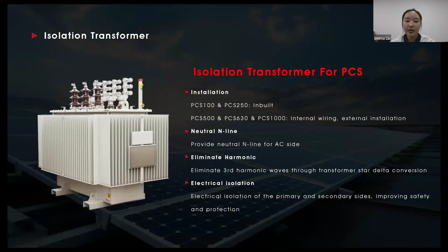One of the unique features of ATESS inverters is the isolation transformer. A PCS inverter used for a large-scale system must be equipped with an isolation transformer. It can provide neutral and line for the AC side, eliminate harmonic waves, and improve safety and protection. The isolation transformer of PCS 100 kilowatt and 250 is built in, and the other 3 models, 500, 630, and 1000, are internally wired and externally installed.